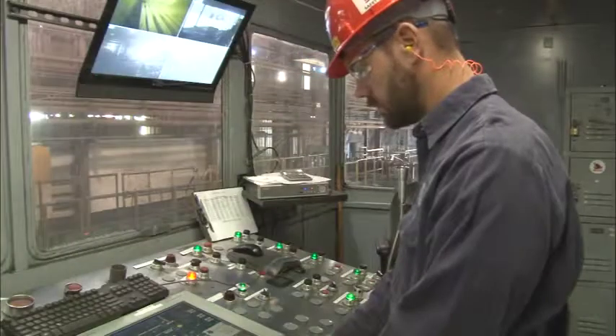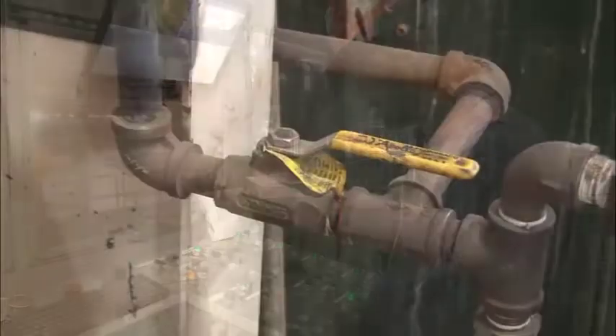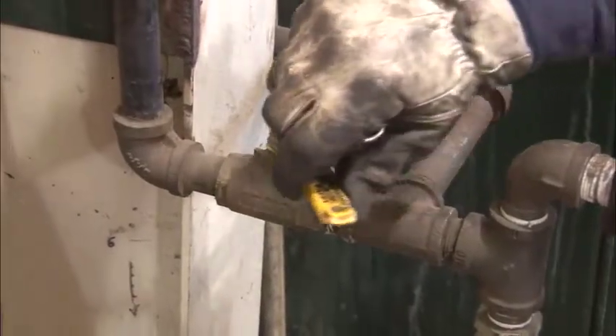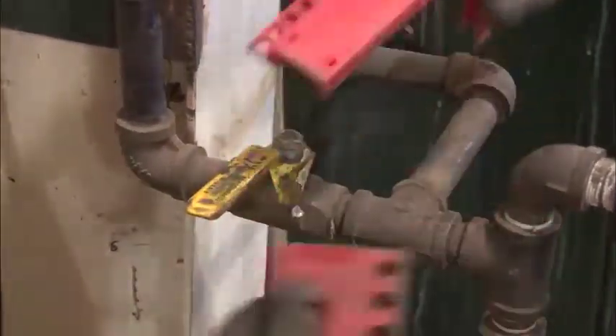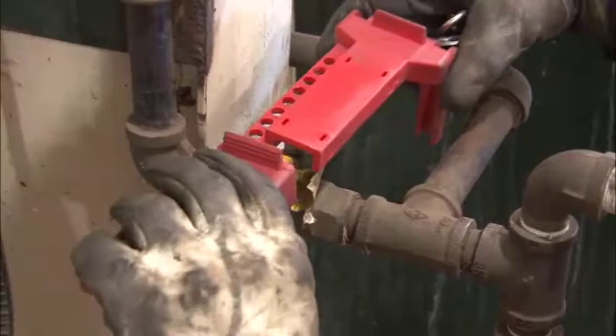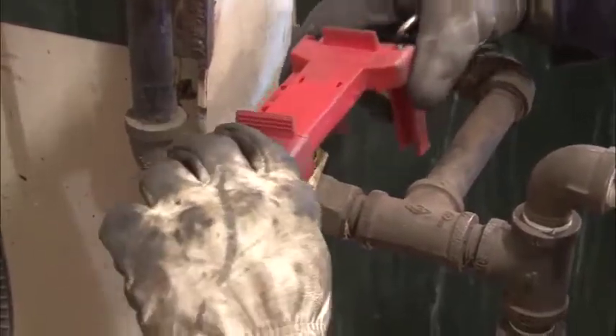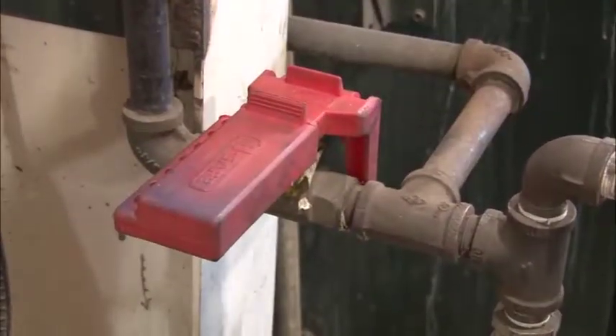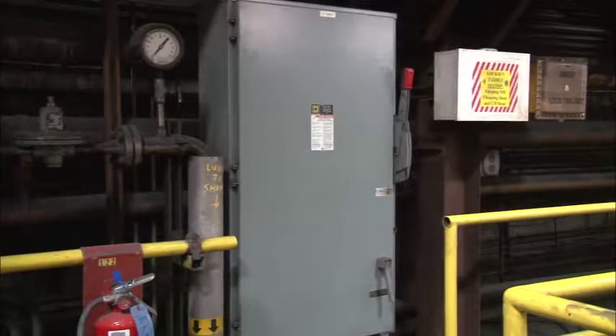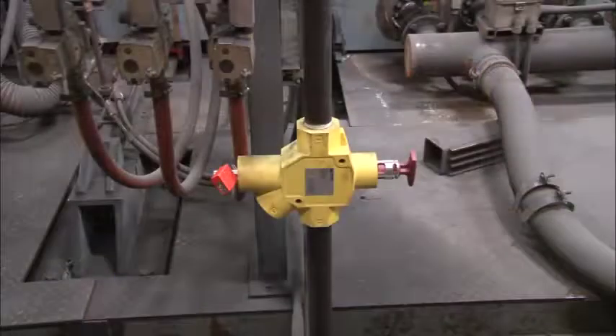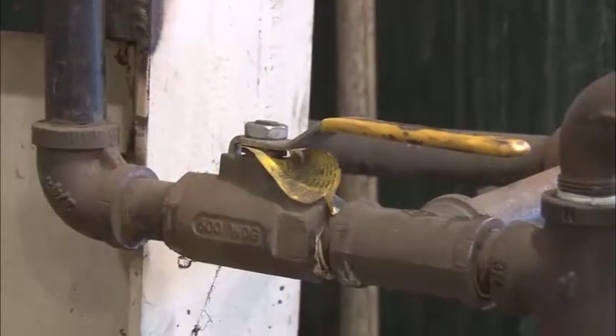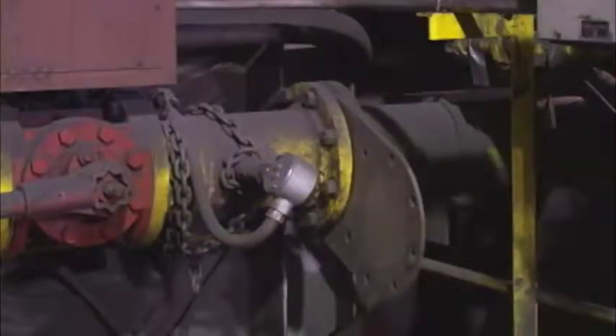The next step is to shut down the equipment. Once it is confirmed that the equipment is shut down, disconnect the power or isolate the equipment from its primary energy source by positioning the energy isolating device in the safe or off position. Examples include pulling electrical disconnects, closing valves on pneumatic, hydraulic, or chemical process lines, or installing blanks.